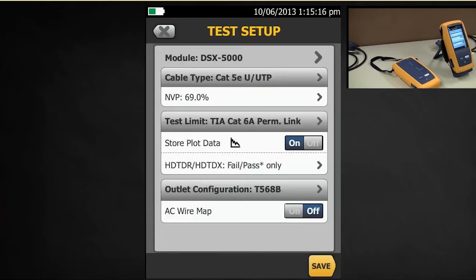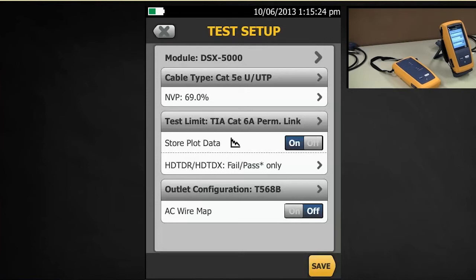Our NVP here is 69%. It's quite important that you check to see what that NVP value is on the datasheet for the cable that you're installing. It will affect the length measurement, nothing else, just the length measurement. We're going to leave it at 69% today.